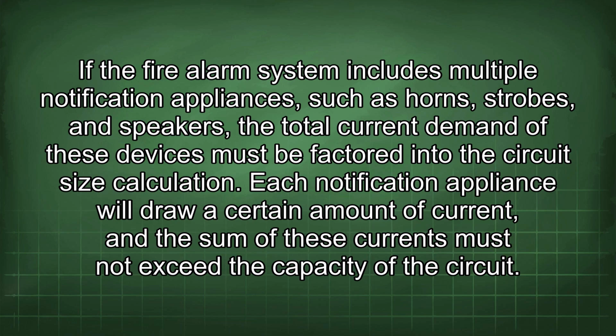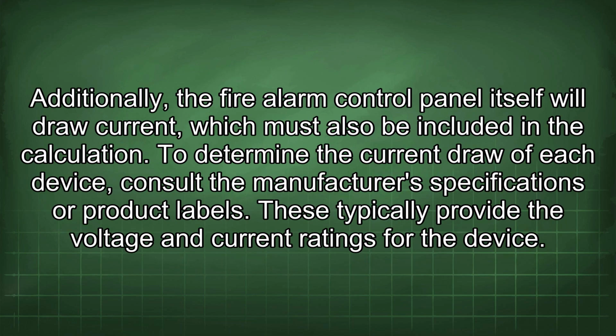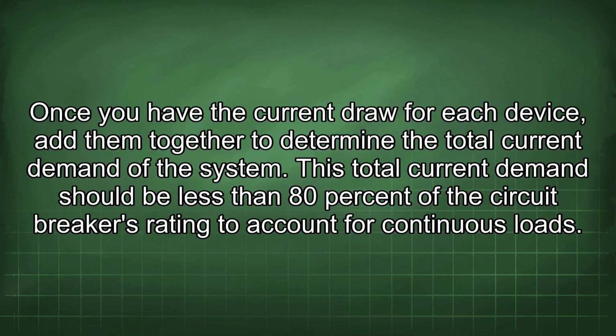capacity of the circuit. Additionally, the fire alarm control panel itself will draw current, which must also be included in the calculation. To determine the current draw of each device, consult the manufacturer's specifications or product labels. These typically provide the voltage and current ratings for the device. Once you have the current draw for each device, add them together to determine the total current demand of the system. This total current demand should be less than 80% of the circuit breaker's rating to account for continuous loads.